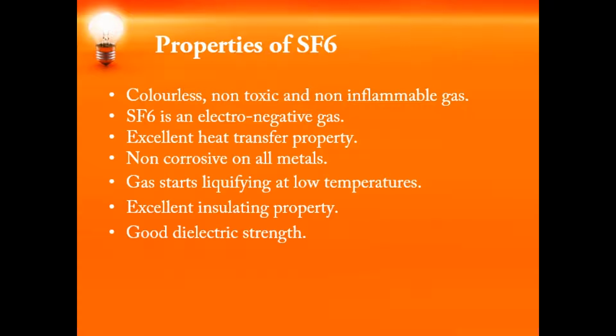It also has an excellent heat transfer property. Its thermal time constant is around 1000 times shorter than that of air. But one disadvantage of SF6 is that it will condense at low temperature, that means it will liquefy at low temperature. So we need thermostatically controlled heaters to maintain the SF6 temperature as required, else it is going to liquefy. These properties of SF6 made it very easy to use as an arc quenching medium in circuit breakers. Moreover, it requires less maintenance as compared to oil circuit breakers.